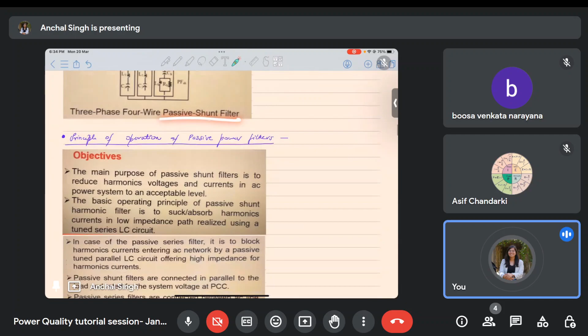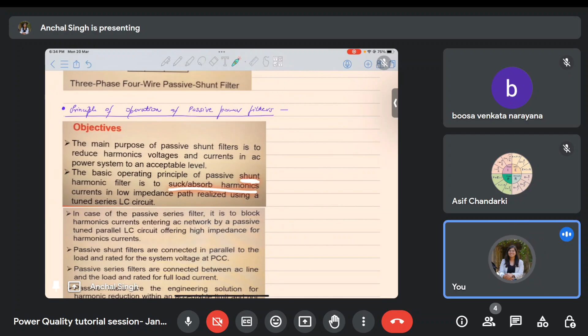Now let us look at the principle of operation of passive power filters. The main purpose of passive shunt filters is to reduce harmonic voltages and currents in the AC power system to an acceptable level. So instead of just focusing on the name, try to focus on the application of these filters. Once you know that you are trying to take care of harmonics, it will be much clearer. The basic operating principle of a passive shunt harmonic filter is to suck or absorb harmonic current in a low impedance path, which can be realized using any R, L and C components.